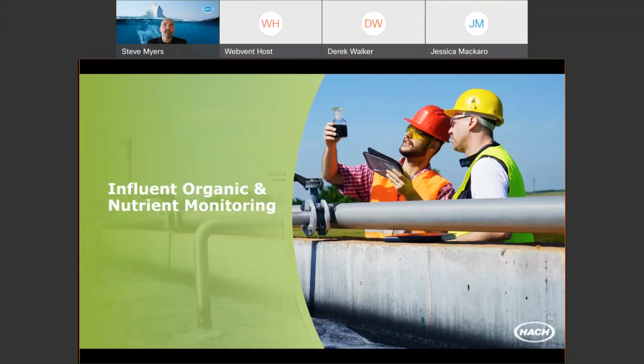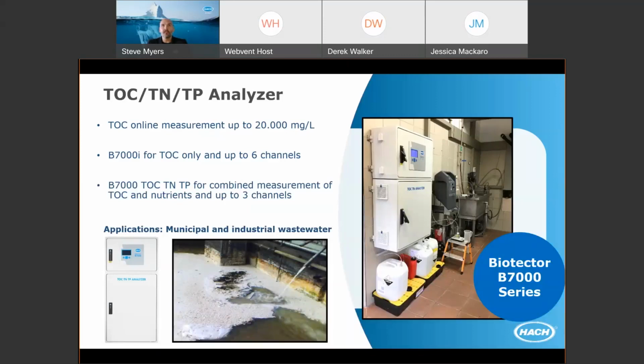So with the wrap up of the online sensors, we're going to transition to some a bit more beefy solutions and some analyzers here. I'm going to kick things off with what we have here, and there's other online organic carbon monitoring solutions out there, but the one that Hach is familiar with is our Biotector B7000 solution. So this unit here is capable of measuring very low to very high organic loads, up to 20,000 milligrams per liter of TOC.